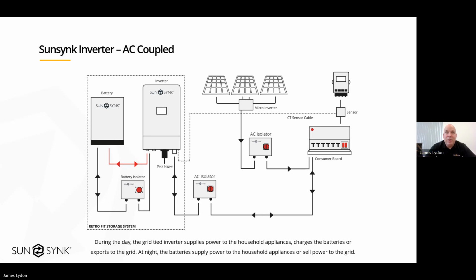When someone is AC coupling and they want to add an Eastron meter to monitor the generation on the string inverter, they would need to use a 3-phase Eastron meter. Even if it's a single-phase supply, it's down to the coding on the Eastron meter. Obviously, they would only use one CT. But yeah, so if someone does want to monitor that extra generation and tie it into our system, even if it's a single-phase grid-tied inverter, they would need to use a 3-phase Eastron meter.